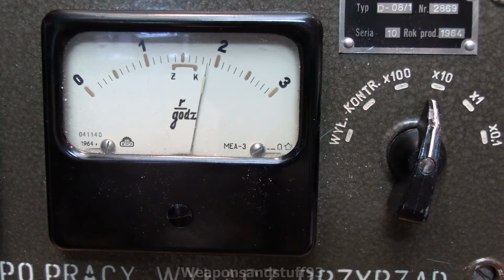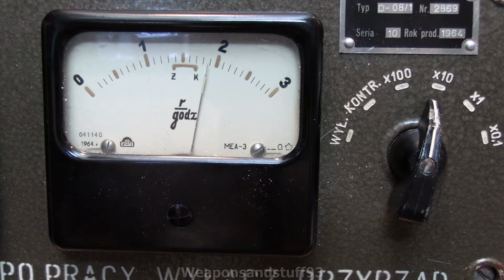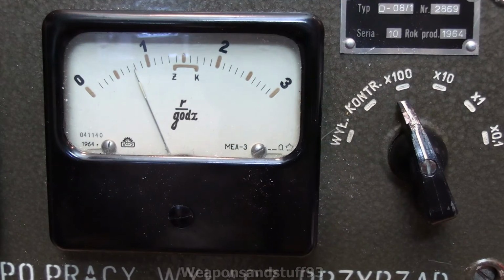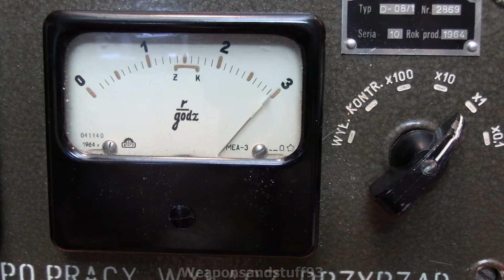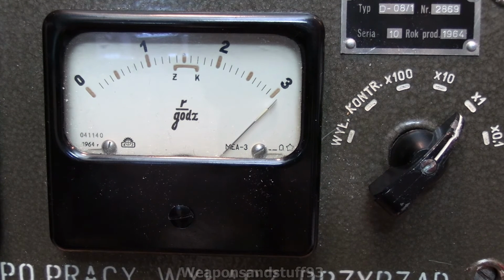I'm just trying to figure out how this is set up then. Because I don't quite get why there's an inner block, then a metal block, and then an outer block, if they all respond. But if it works, it works. I've never noticed that before. So if I go down a scale, it should go off scale. Let's just try that. I've gone up a scale, haven't I, there? So we go that way. So that should peak at 3, if this is going to give the same reading on this one. So, yep, that's gone off scale at 3. You can see it hovering around the 3 area. So weirdly, that is like 3.6 Rontgen where the scale goes off.